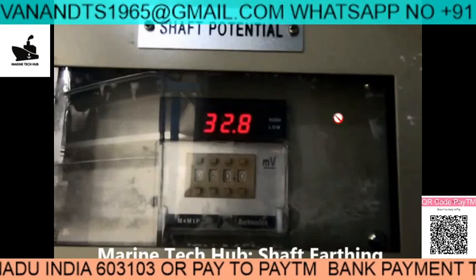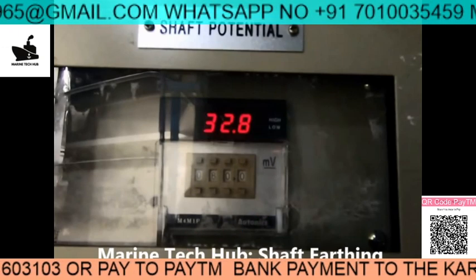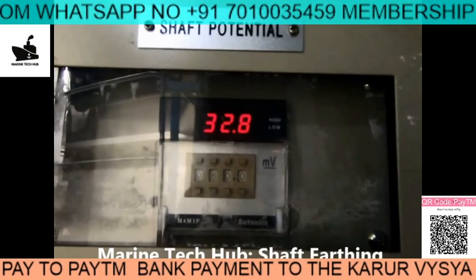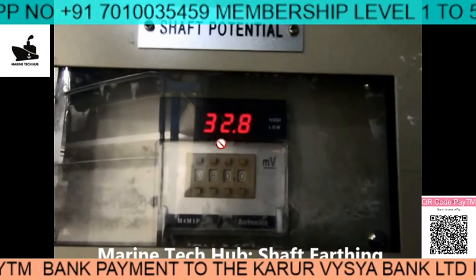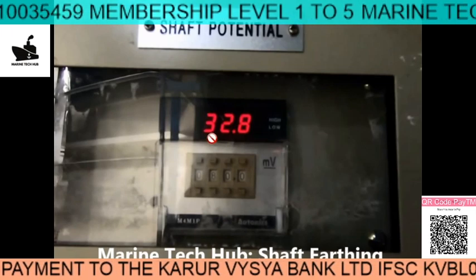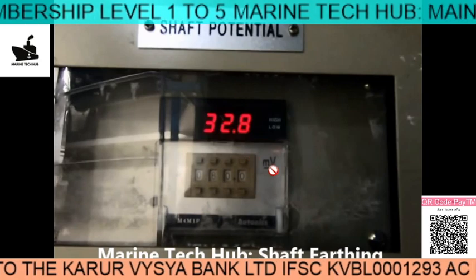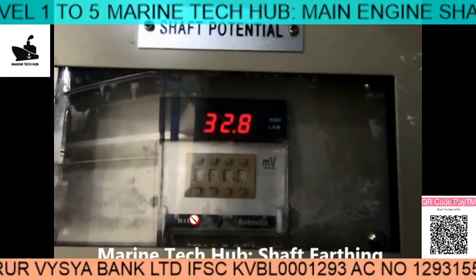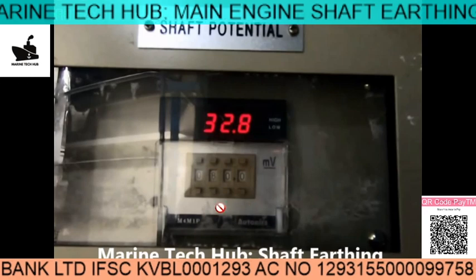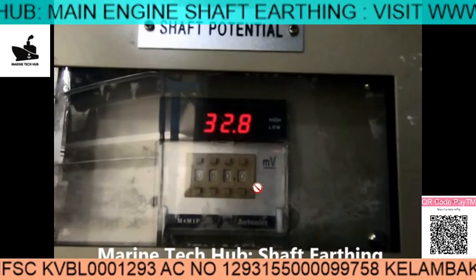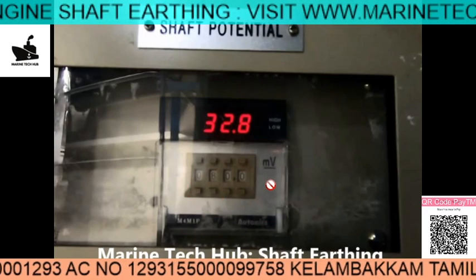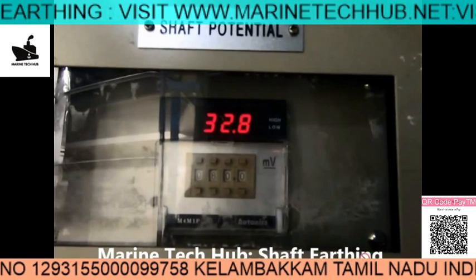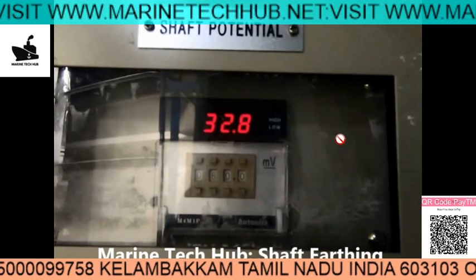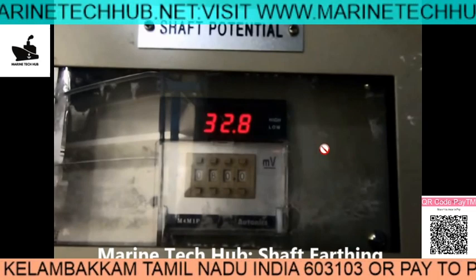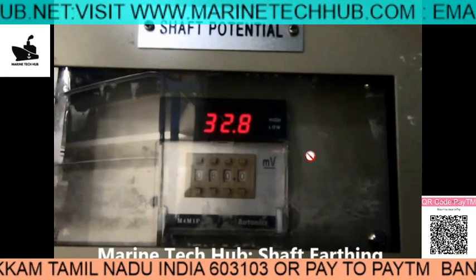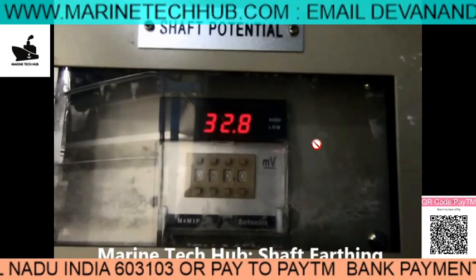Welcome to Marine Tech Hub. Today I'll be explaining shaft earthing. In this picture you can see the reading is 32.8 millivolts, and right now the main engine is running. Any value between 0 to 80 millivolts is acceptable. The purpose of shaft earthing is very important, and if the reading is more than 80 millivolts, you have to check what the problem is.